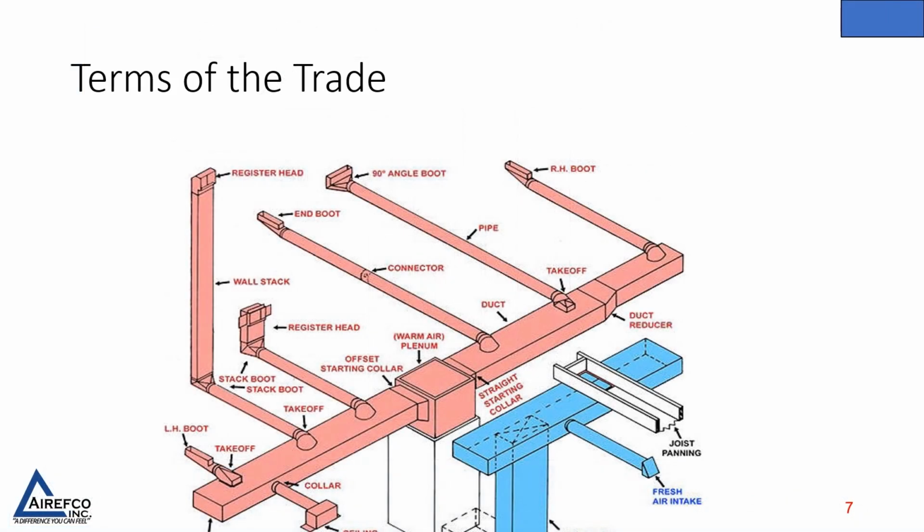Once we have verified that we have the proper airflow through the furnace, then we want to make sure that we have the ductwork laid out so that we have the maximum amount of airflow throughout the entire system. There are many types of ductwork, hard duct and flex duct, and all of these need to be checked along with each register and the type of transition that you have to make sure that we don't have excessive ductwork in the system.